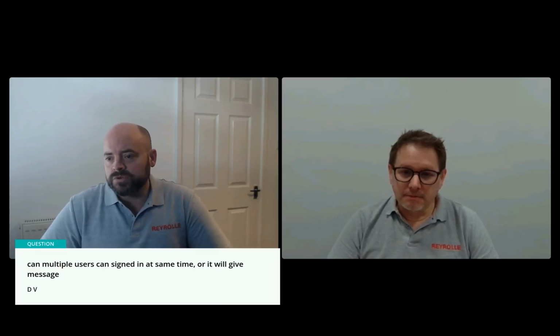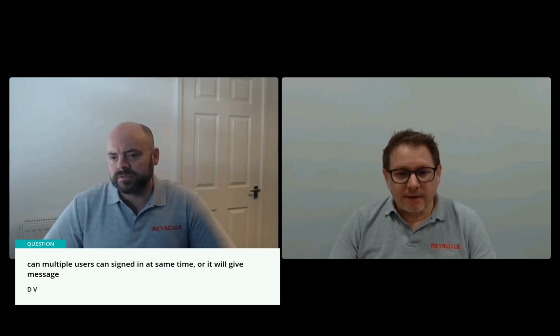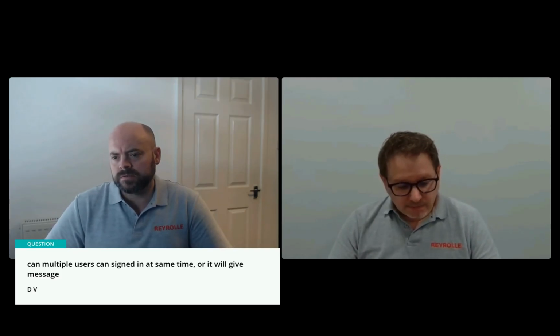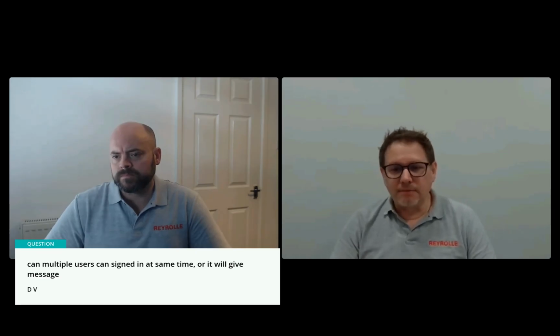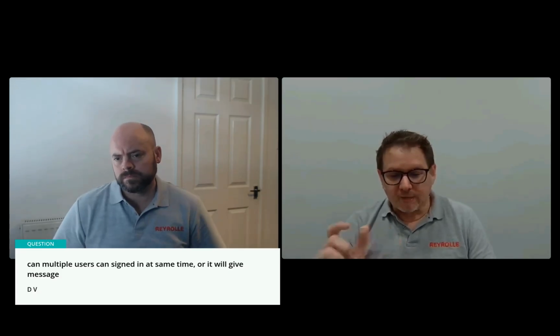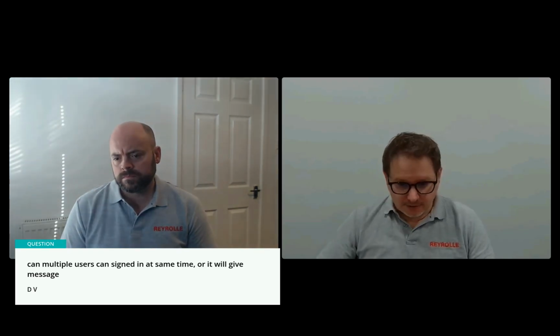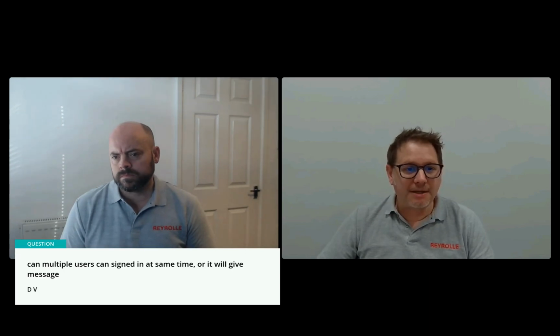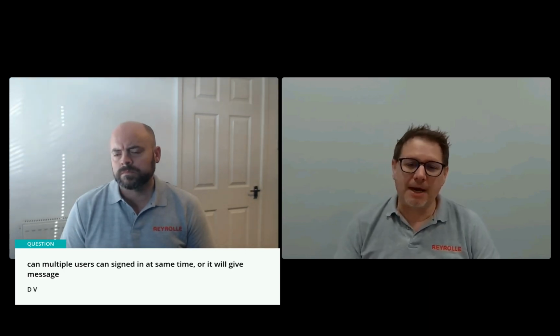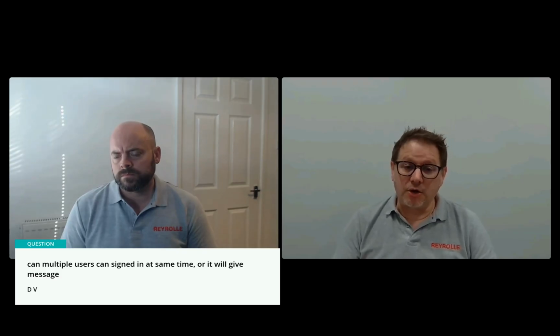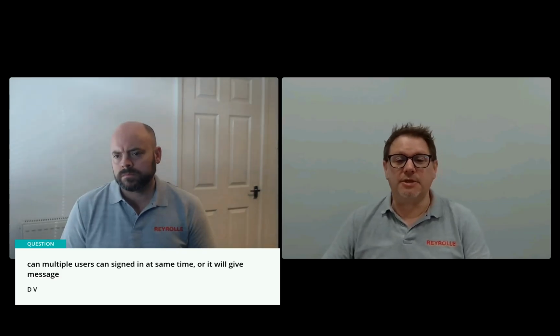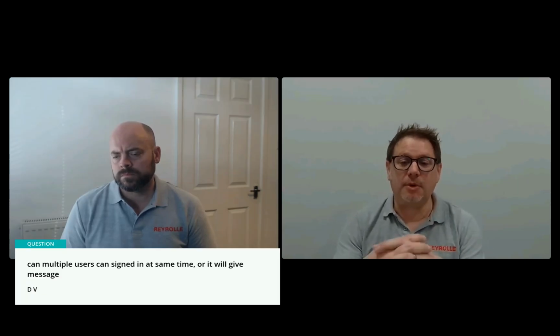Next question we have from DV. Can multiple users be signed in at the same time, or will it give an error message? Yeah, when you log in remotely, you have the session. Every user has their own session. We configure in the security settings the number of sessions available. I'll just check, I can't remember how many it is. Three by default, and you have a maximum number of 10 sessions concurrently open. So that would allow up to 10 users to concurrently access the device remotely.